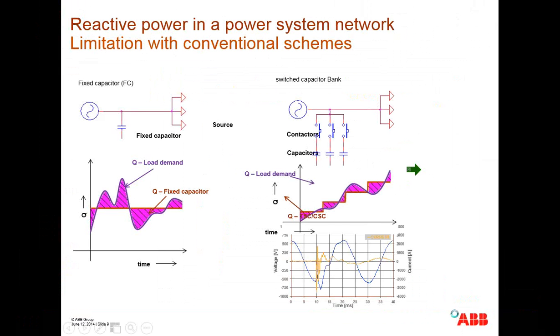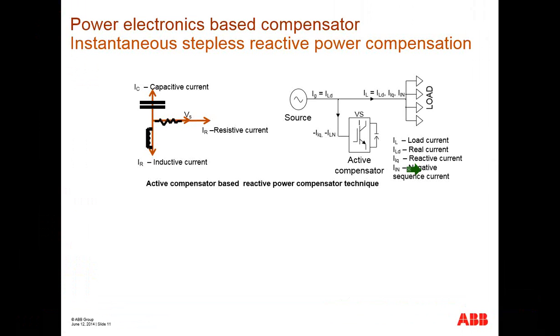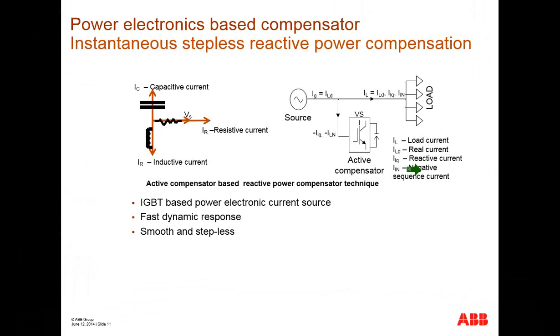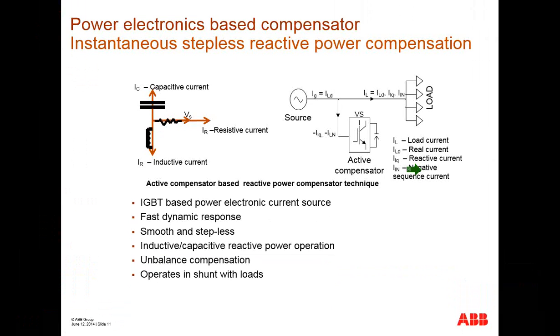And the response time, which is very crucial here, is basically IGBT based converter. You can see it can generate both capacitive as well as inductive, and this is a very fast and dynamic response. The smooth and stepless compensation can be fraction of kVAr or fraction of unbalanced compensation. It can generate both inductive as well as capacitive reactive power, unbalanced compensation, and operation in shunt with the load.